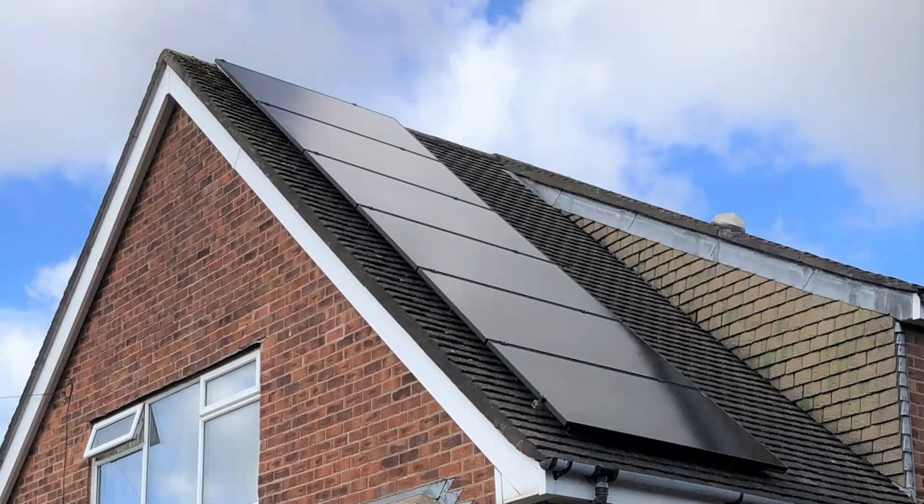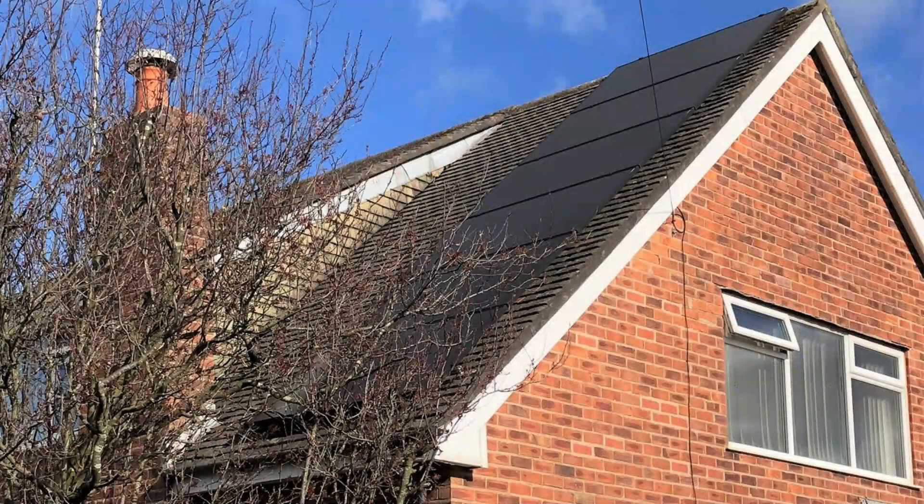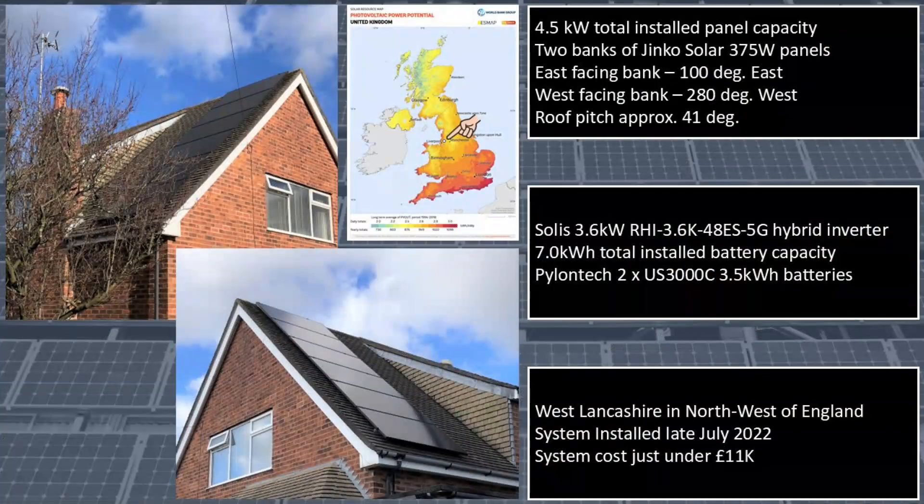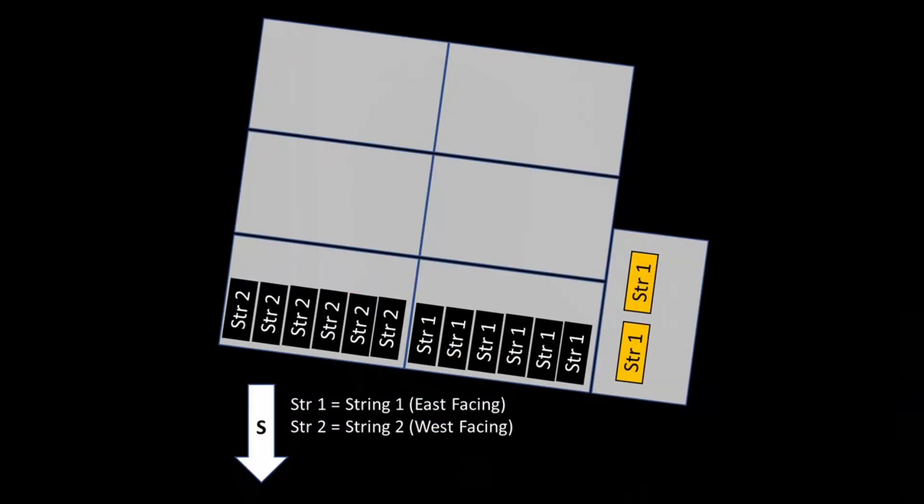Our original installation comprised two banks of six Jinko Solar 375W panels installed on broadly east and west facing roof pitches. When adding the two new panels, to keep costs down I chose to connect them in series with the existing east facing string, so no additional inverter was needed. They were a good match with the Jinko panels in terms of voltage and current.